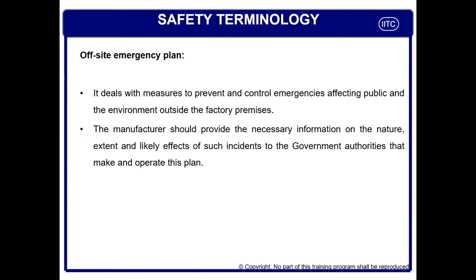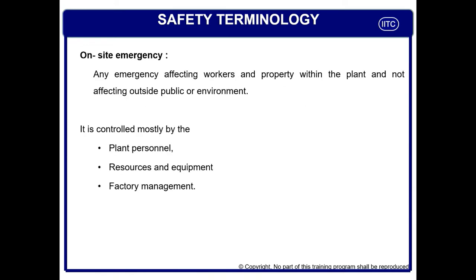Each manufacturer of hazardous chemicals or hazardous operations must give information to their district administration about the possible emergencies which can happen in their plant and which can affect nearby populations, nearby companies, and nearby societies — and if that event happens, how to minimize damage, control injuries, and control fatalities. This must all be defined in the off-site emergency plan. An on-site emergency plan is an emergency affecting workers and property within the plant and not affecting the public or environment outside. Normally it is controlled by plant personnel, plant resources, plant equipment, and factory management — requiring no support from district administration, police, or traffic police.